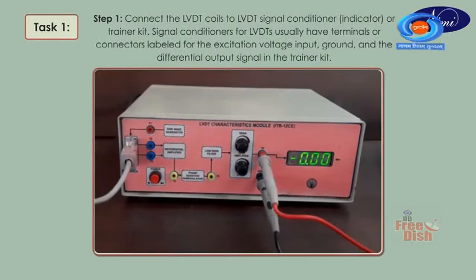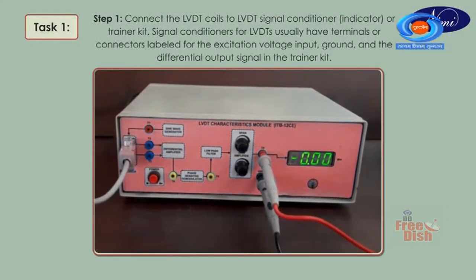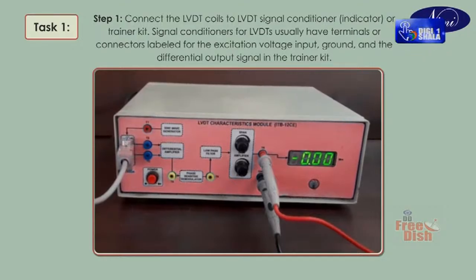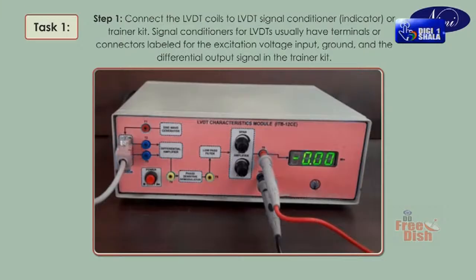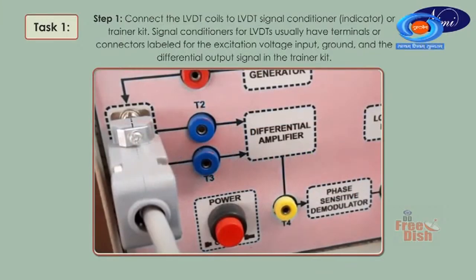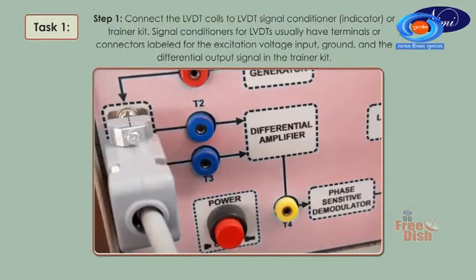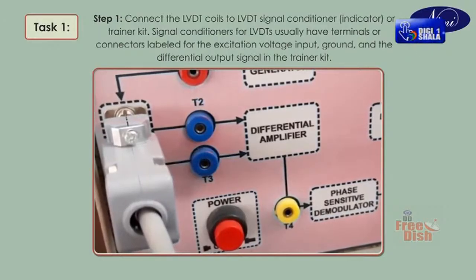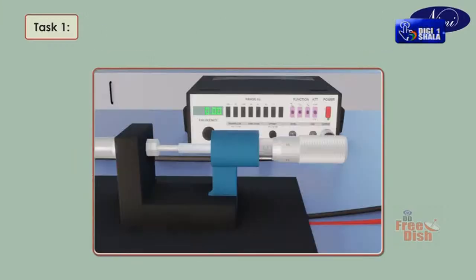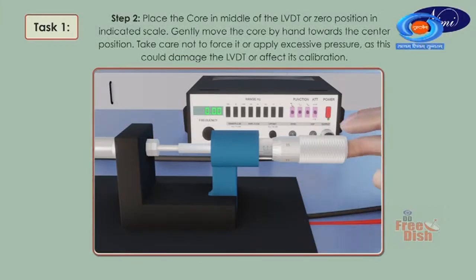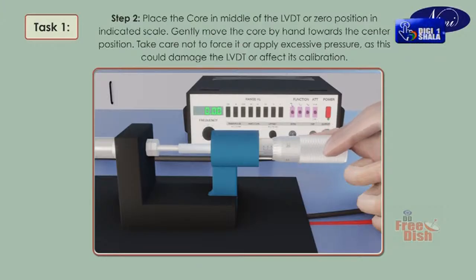Step 1. Connect the LVDT coils to LVDT signal conditioner, indicator or trainer kit. Signal conditioners for LVDTs usually have terminals or connectors labeled for the excitation voltage input, ground and the differential output signal in the trainer kit. Step 2. Place the core in middle of the LVDT or zero position in indicated scale. Gently move the core by hand towards the center position. Take care not to force it or apply excessive pressure, as this could damage the LVDT or affect its calibration.